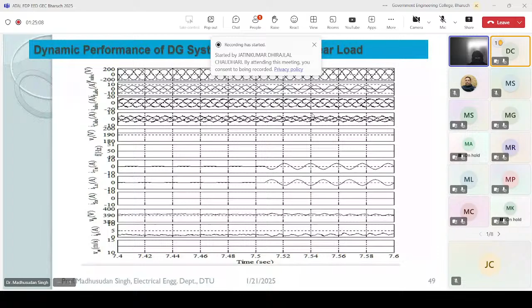These are a few energy balance, the power balance equation. Power balance profiles are also shown here. You see that includes the generator power, the load power, and the battery power. So you see the generator operates almost at a fixed power. So this is how it ensures that the frequency of the generator remains the same. If there is a variation in the load power, it is being picked up by the battery. So the generator is operating at its full rated power, and that's why the frequency remains 50 Hz.